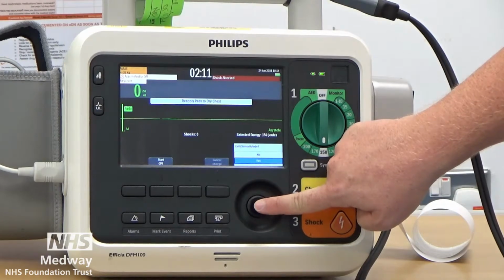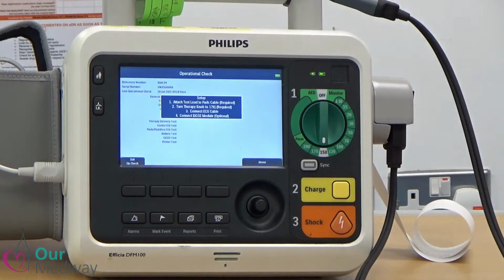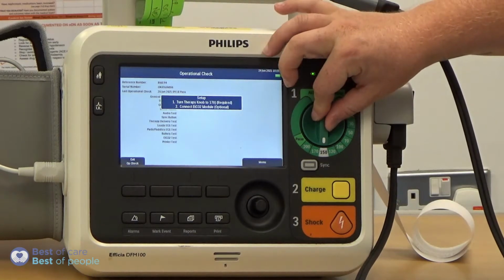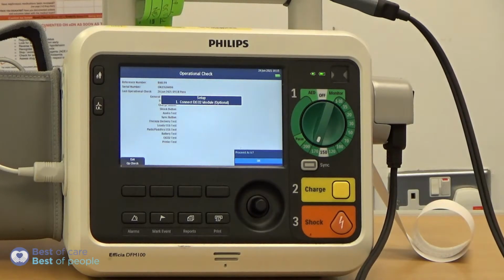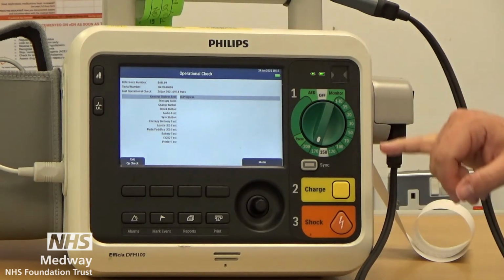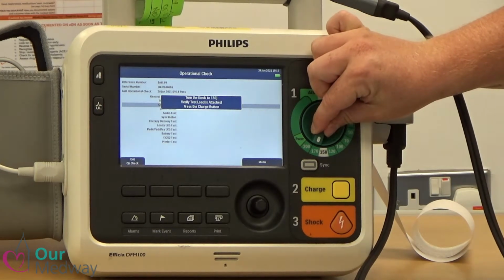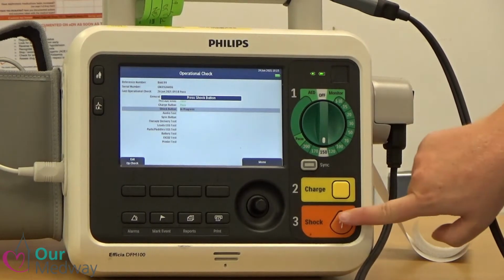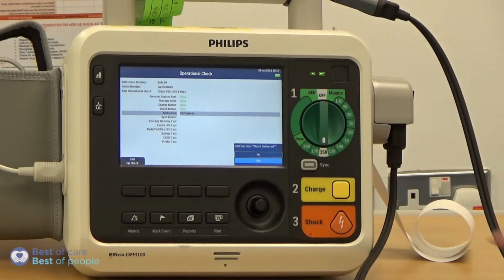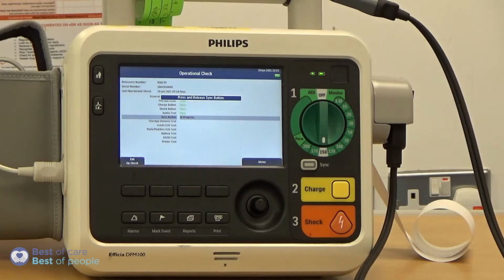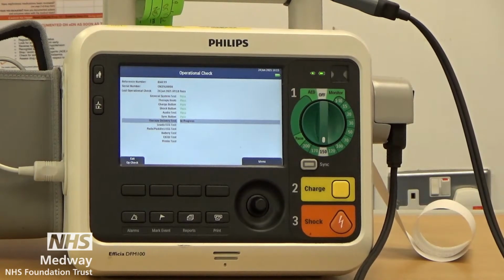And then the defib will simply give you instructions and it will want you to do a series of tasks to check that it's working. And we follow the instructions. So the first thing it's asking me to do is to turn the therapy knob to 170, which I will do. It is asking about the end tidal and it's saying that it's not connected. We know that, so that's fine. I'll click OK and you'll see that it will work its way through. Turn to 150 and press charge. Press shock. Shock delivered. It will ask if I heard that. Did you hear that? Yes, I did. Press and release the sync button. And the majority of the checks it will run for itself. So it'll be checking the battery and some of the leads. Doesn't take too long to complete the rest of these checks.